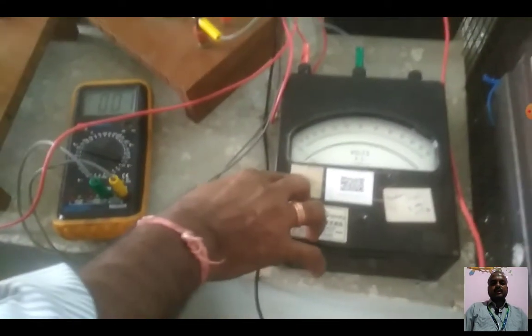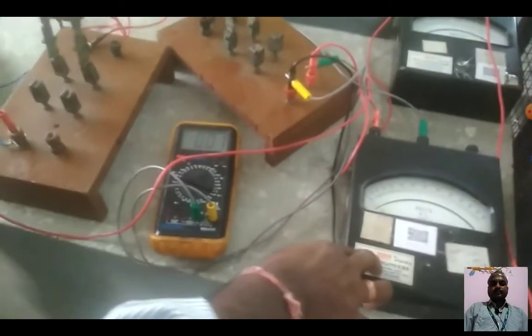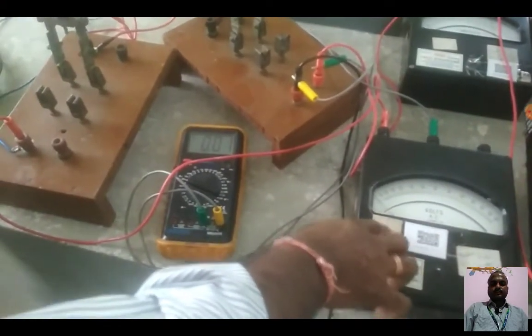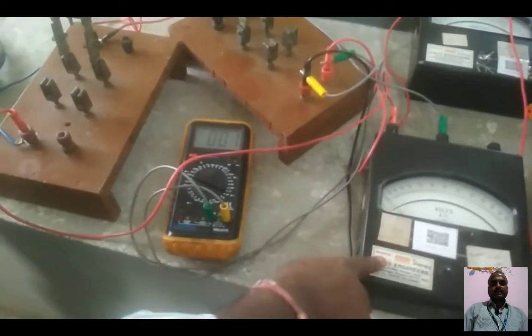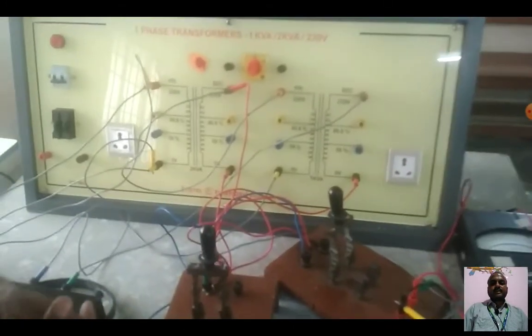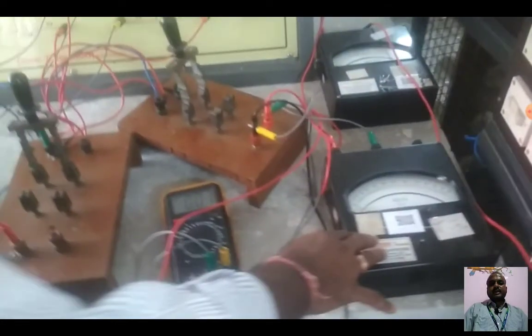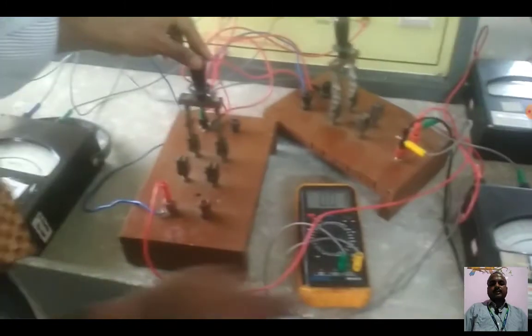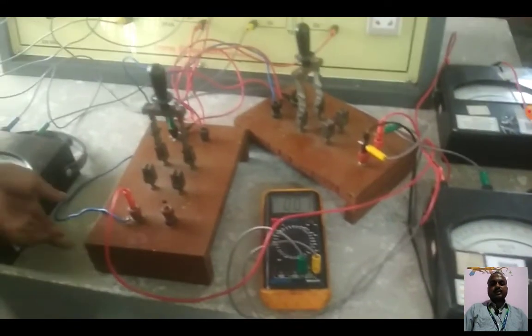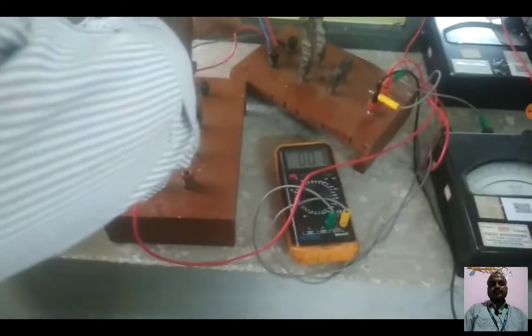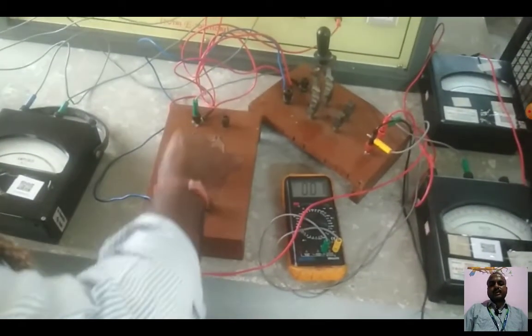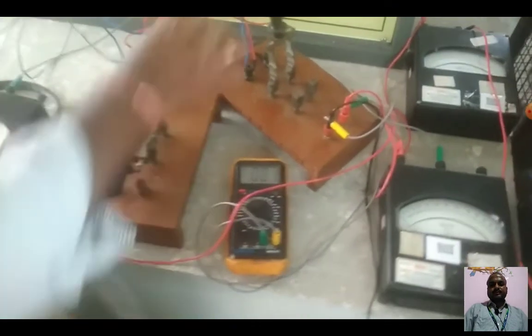Then check the voltage across the SPST switch. It is showing 0. With 0 voltage, the polarities of the transformers are correct on the secondary side of the power transformers. Otherwise, you have to interchange the secondary side terminals of any one transformer. Once it is showing 0, close the SPST switch. Now we are closing the SPST switch here. Then close the load switch, that is, the DPST switch.